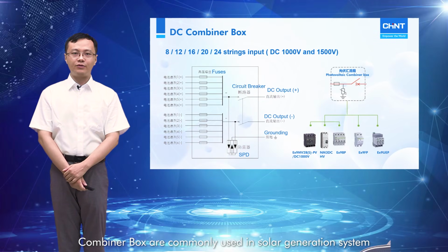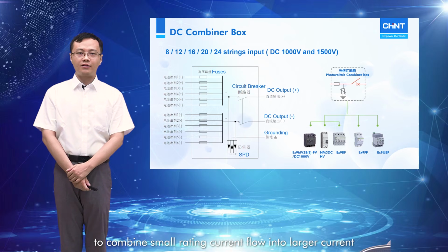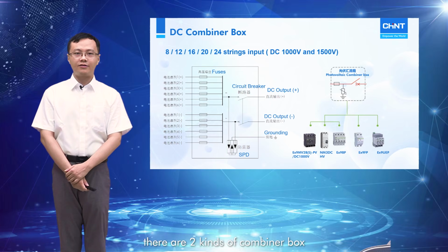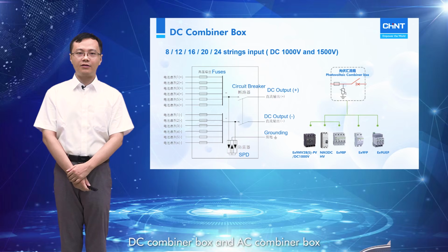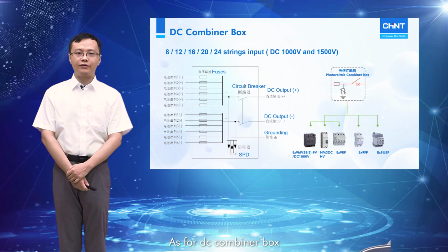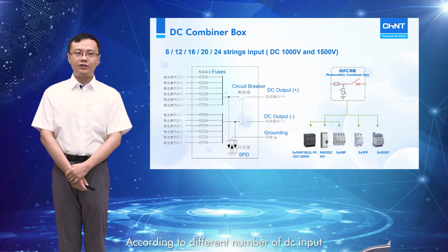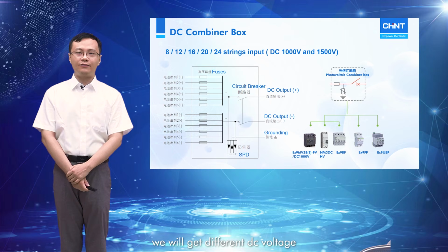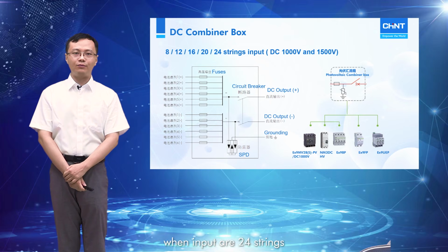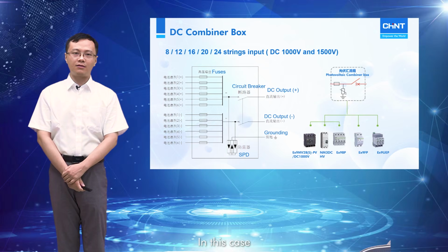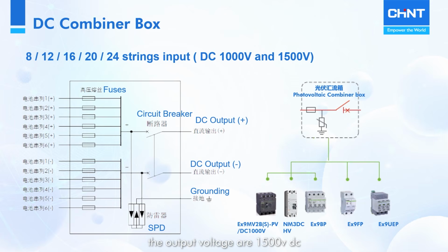Combiner boxes are commonly used in solar generation systems to combine small rated current flows into a large current. There are two kinds of combiner box, DC combiner box and AC combiner box. DC combiner boxes are normally used in centralized solar generation systems. According to the different number of DC inputs, we get different DC voltage. For example, when the input is 24 strings, the output voltage is 1500 volts DC. The DC type fuse EX9PF, SPD EX9UEP, DC type MCB EX9BP, and MCCB NM3 DC HV can be applied.